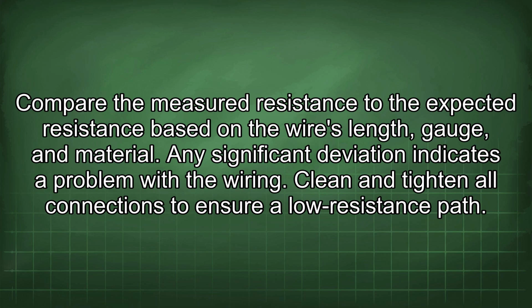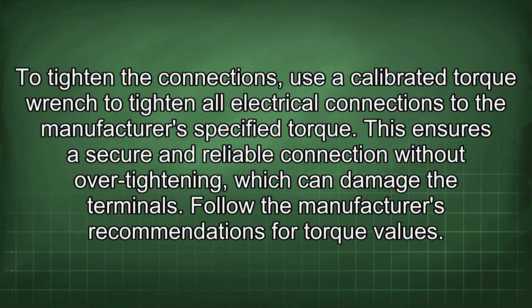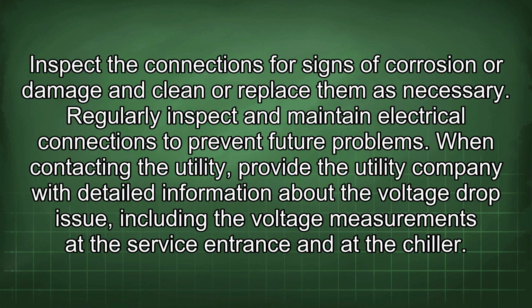Clean and tighten all connections to ensure a low resistance path. To tighten the connections, use a calibrated torque wrench to tighten all electrical connections to the manufacturer's specified torque. This ensures a secure and reliable connection without over-tightening, which can damage the terminals. Follow the manufacturer's recommendations for torque values. Inspect the connections for signs of corrosion or damage and clean or replace them as necessary. Regularly inspect and maintain electrical connections to prevent future problems.